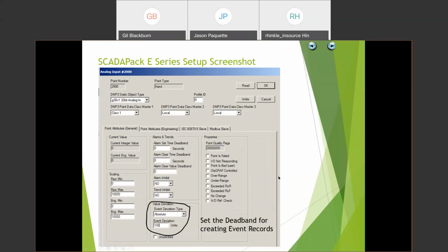Here's an example of an analog point. There again, group 30, variation 1, 32-bit analog in, class 1. Here, it's 0 to 10,000 is what the scaling is. Every 100 units, it's going to generate an event log in the RTU. So when it's polled or we get an alarm, it'll send that in.